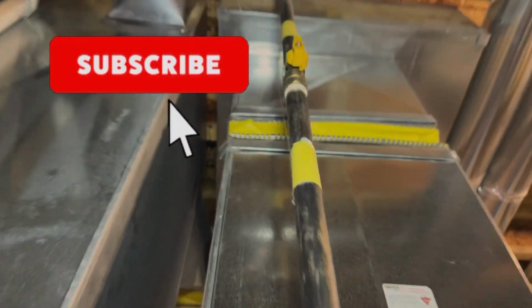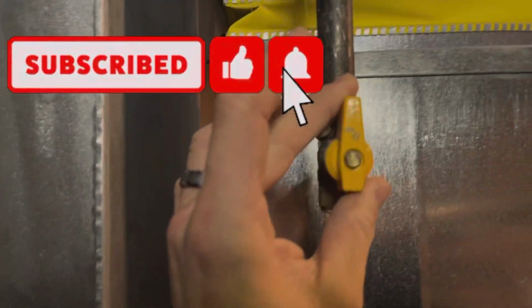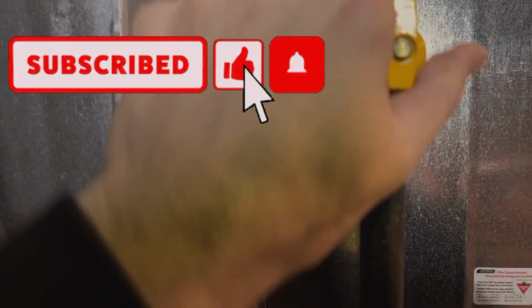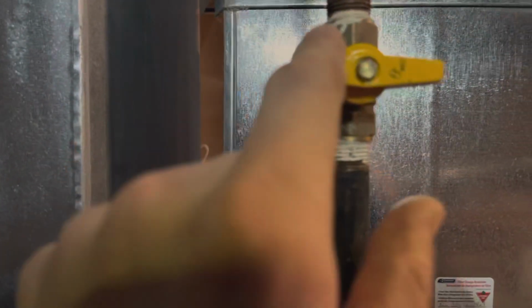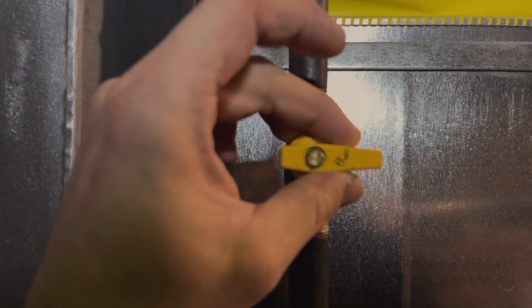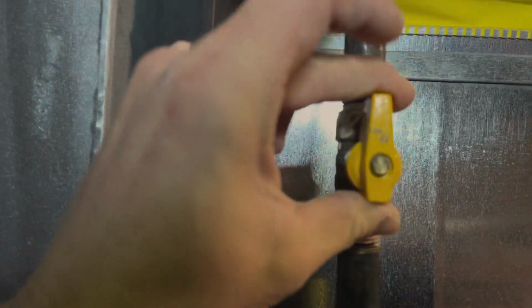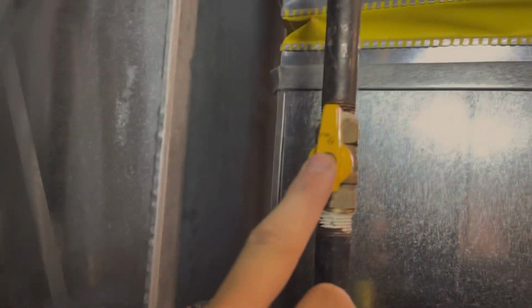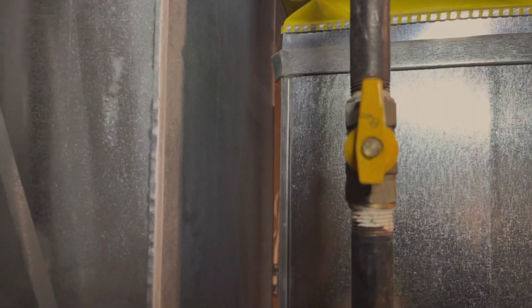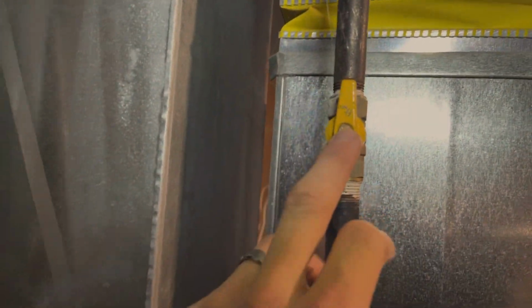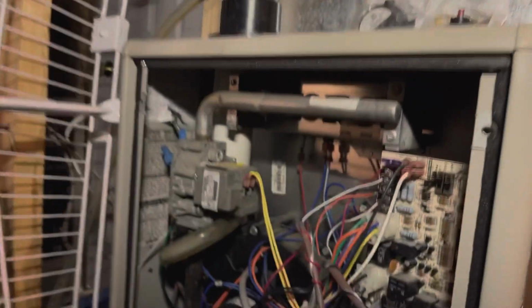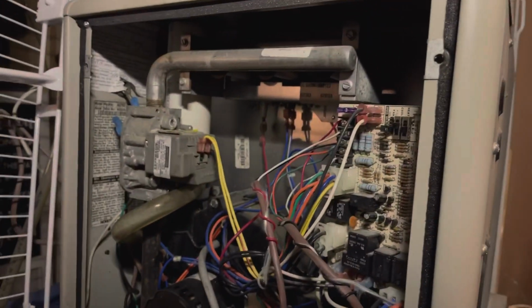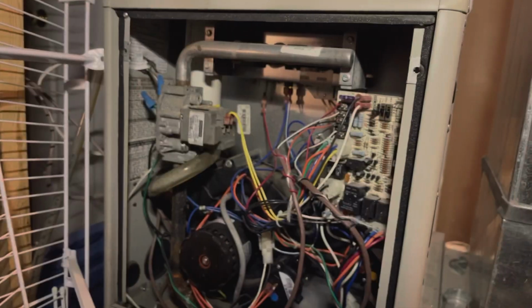Another issue you could have is your gas line. So the inline valve is on if it's parallel, and if it's turned off, it's going to be perpendicular. So somebody could have shut that off. Maybe somebody was working on your furnace and shut that off and forgot to turn it back on. So check that, obviously, to make sure you have gas to your furnace, whether it's natural gas or propane. This is propane, but very similar for natural gas furnaces.